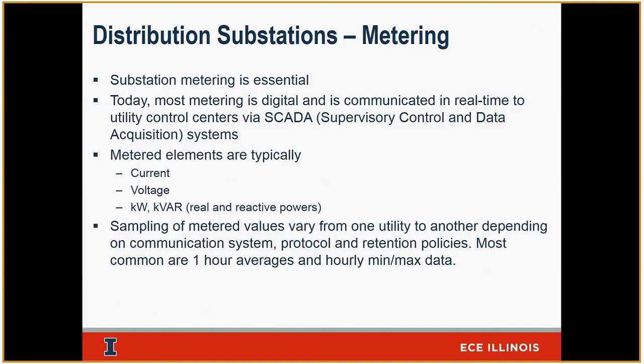What's very important for us, especially today in the modern world of smart grid, is metering. What that means is I want to be able to get as much information as possible off all my devices. So at Ameren, we try to meter the substation transformer. Off this, I know what the voltage is, what the watts are, what my VARs are, and what my amps are. These are the main four criteria I'm bringing back on every transformer, on every feeder.